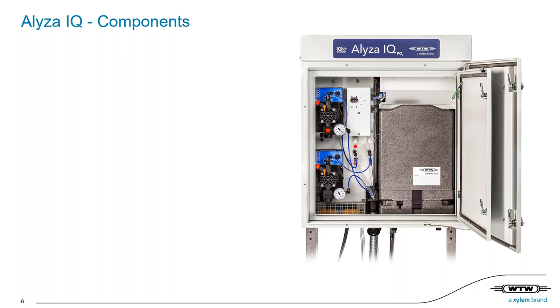Now, I would like to review some of the main components of the new analyzer, in this case a two-channel version. I'll just take the direction of the sample flow now. These are the two filtration pumps with individual pressure sensors. The results of these sensors can be used to check if a cleaning of the filter is required or if the sample tubing might be clogged.